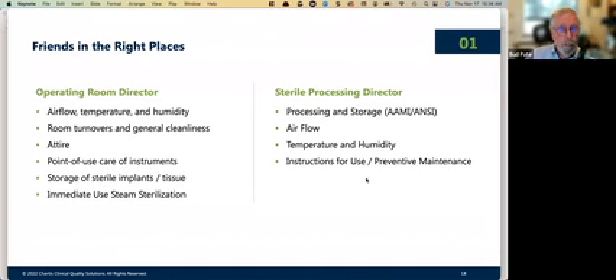In the procedural setting, there's one other place that folks get into trouble, and that's usually the airflow to the equipment room or the decontamination room into the sterile processing room or other sensitive areas. Checking that airflow is just a problem. It's like painting the Golden Gate Bridge. Once you get done, you need to start over again, because the air balancing of those is very sensitive and very multifactorial. So that's something you want to check regularly, especially if it's in your survey time, because you know they're going to do smoke testing or something else on the airflow.